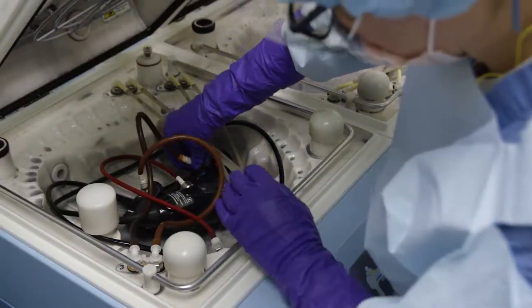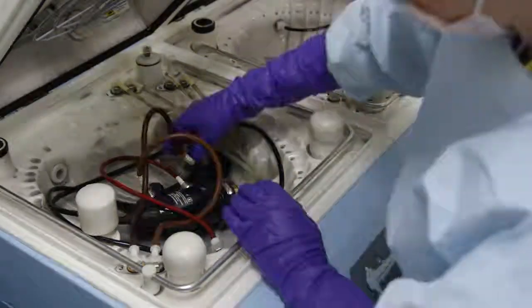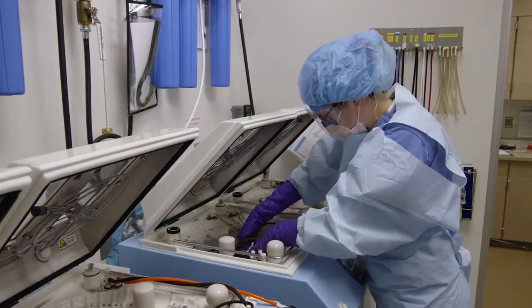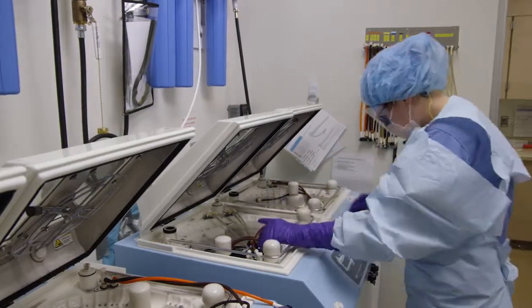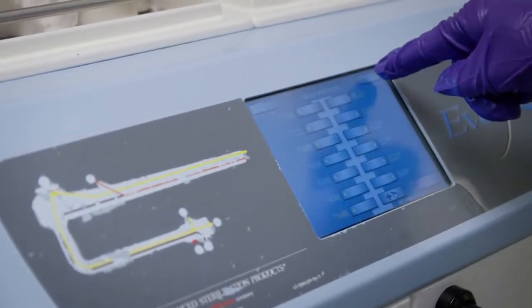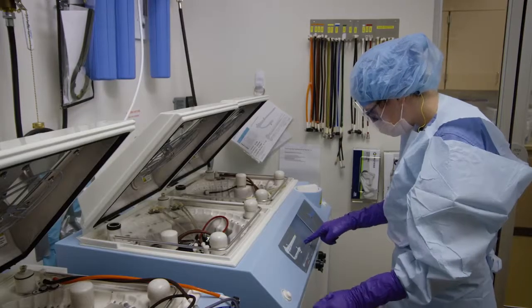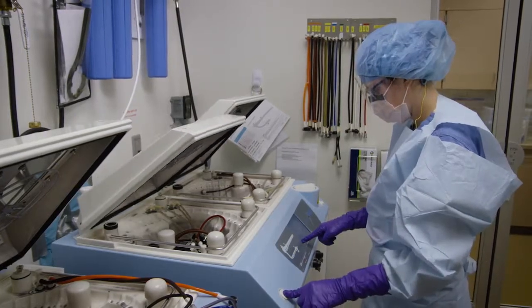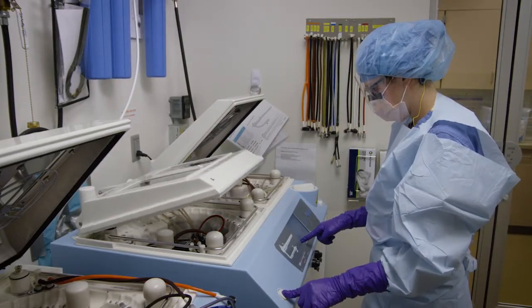Once the scope has been placed into the reprocessor and properly connected per endoscope manufacturer IFUs, input data regarding the patient and load into the AER if that feature is available. Start the reprocessor and allow it to complete all cycles and phases.